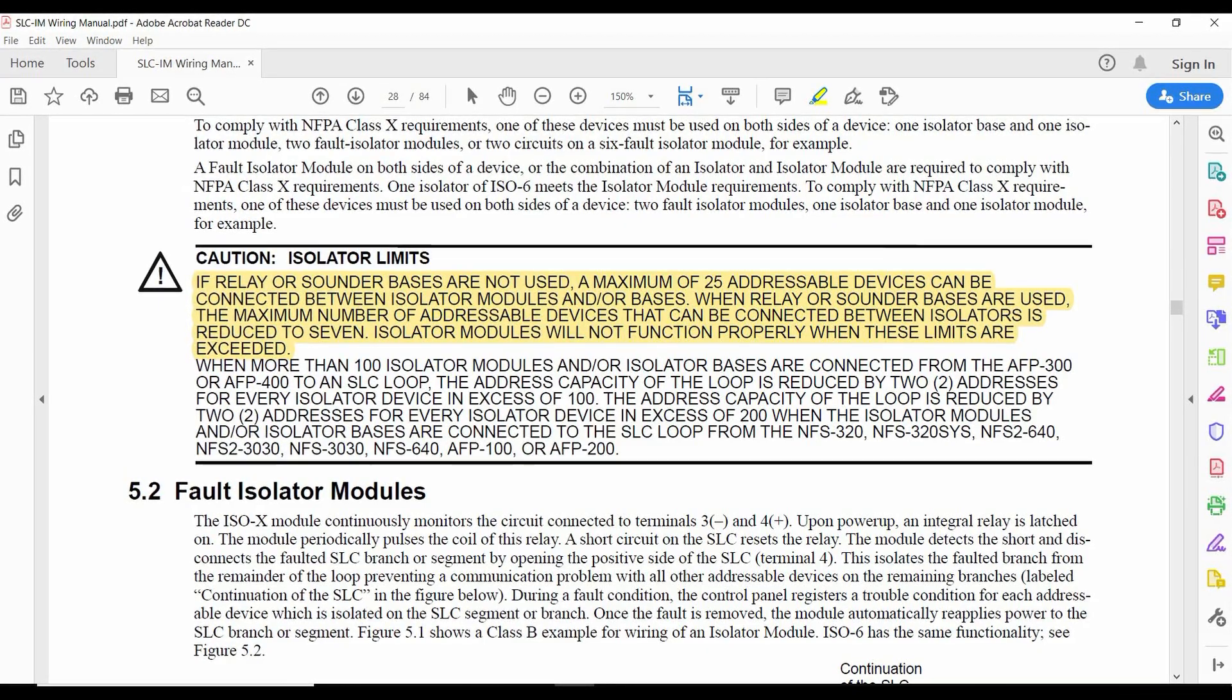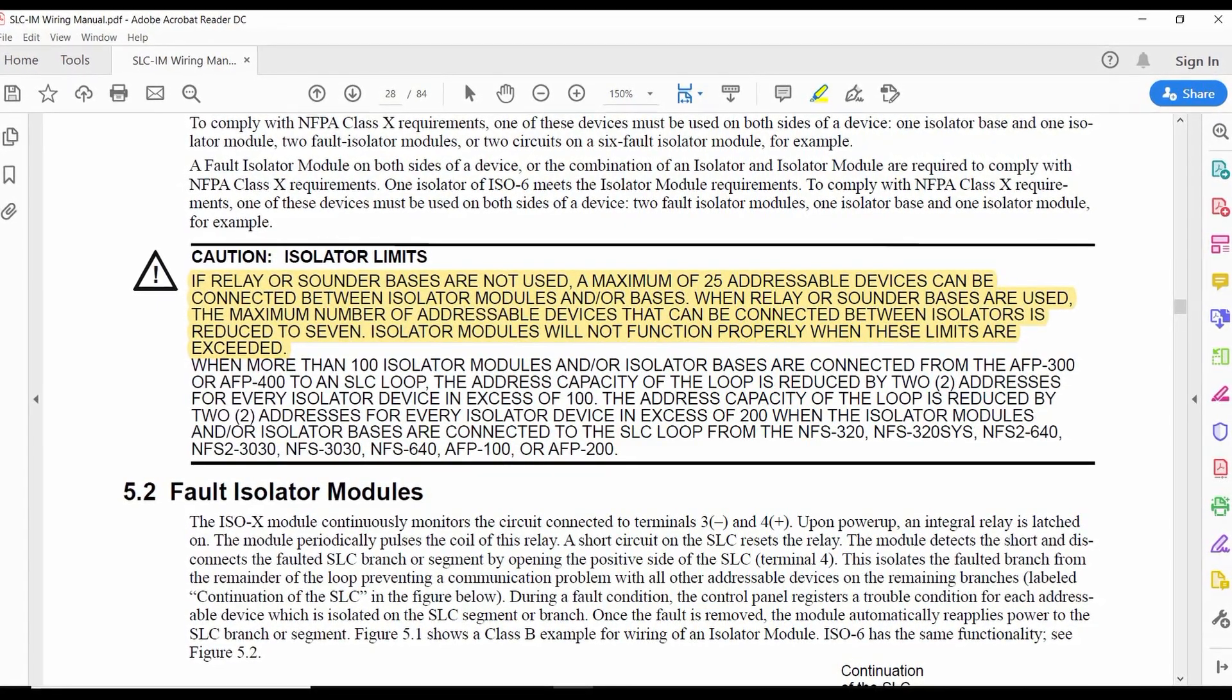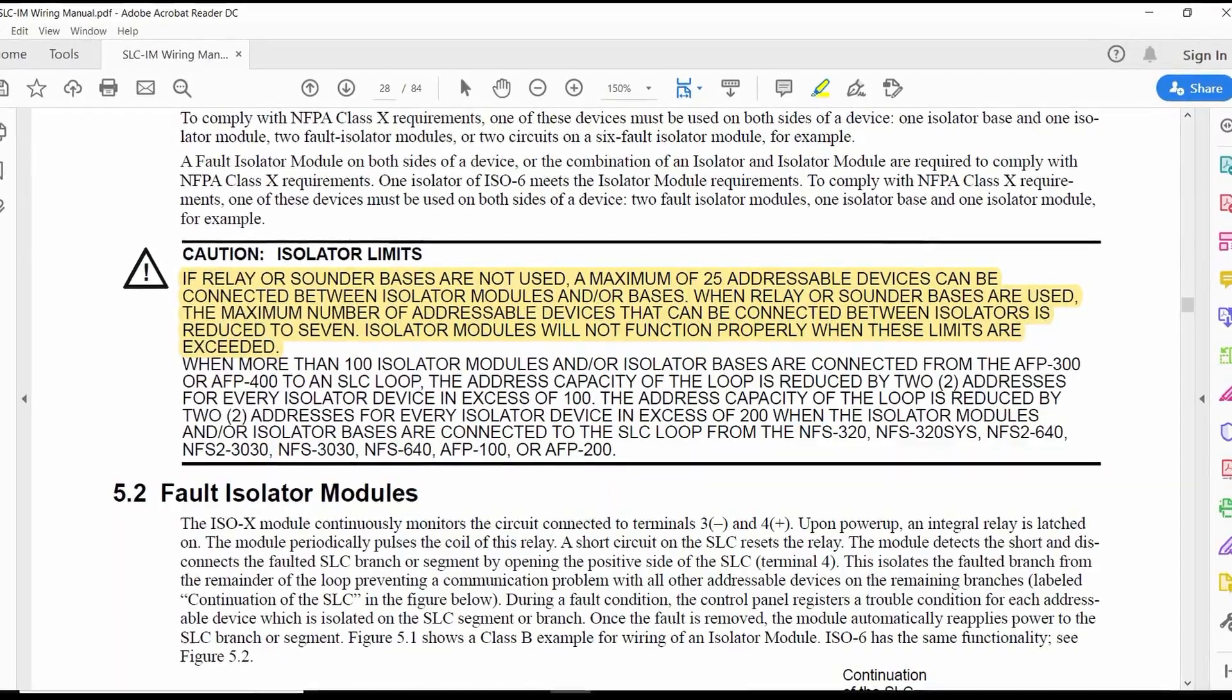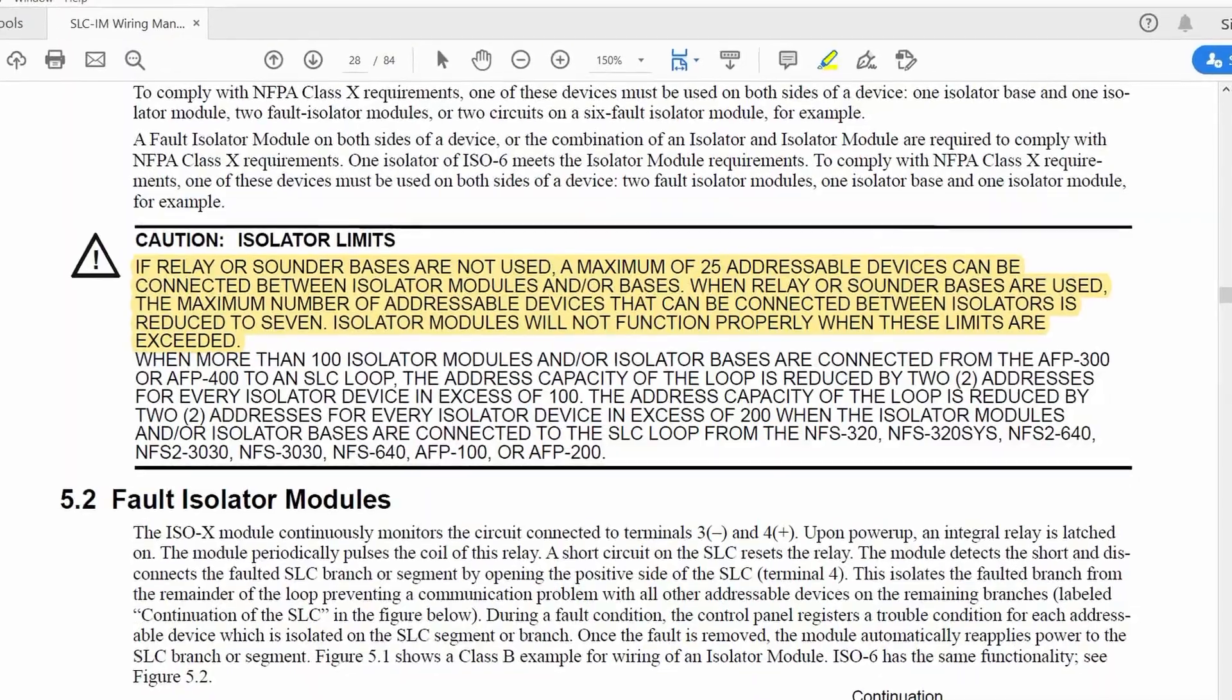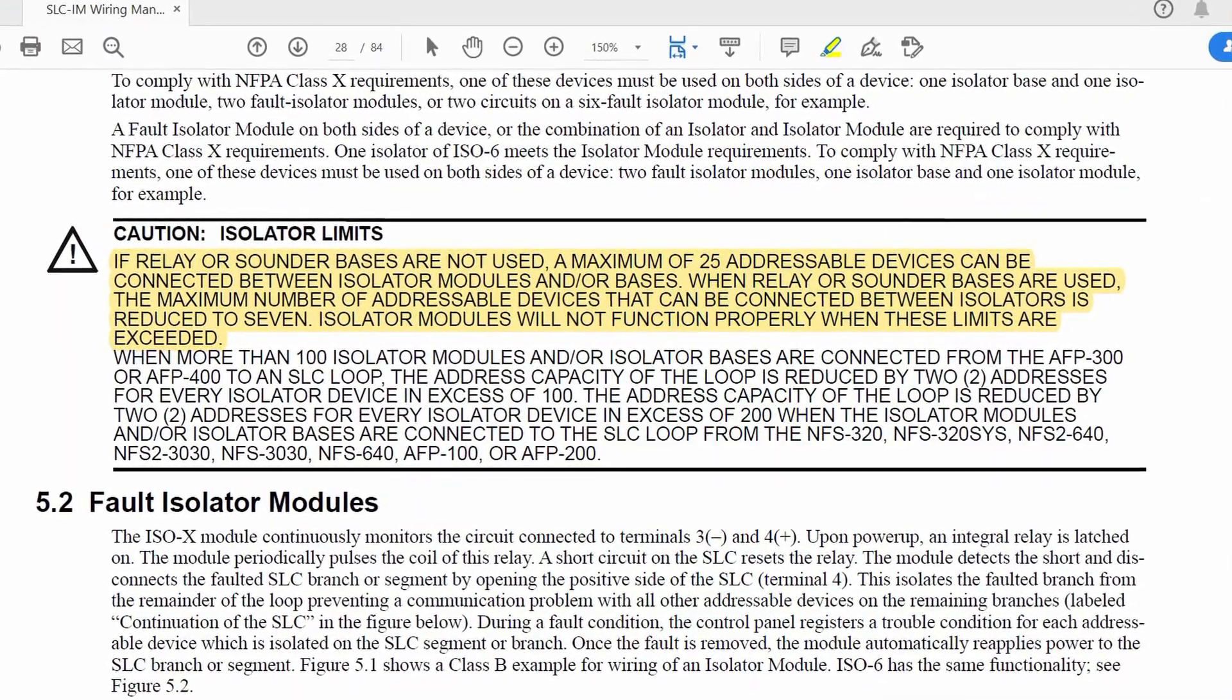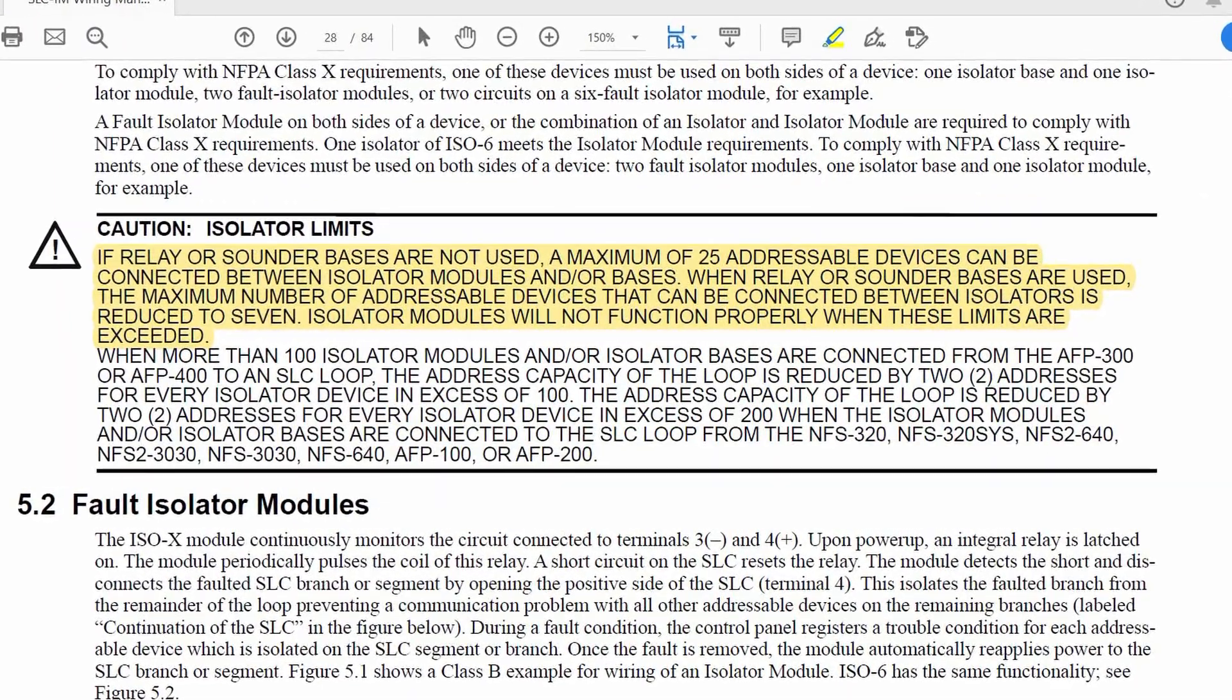Isolator modules come with some limitations that need to be considered. Only 25 devices can be installed between isolator modules for them to work properly, and that number is reduced to seven when either relay modules or sounder bases are being used.